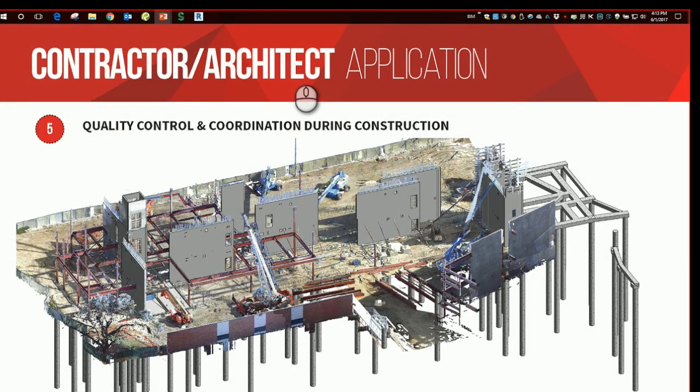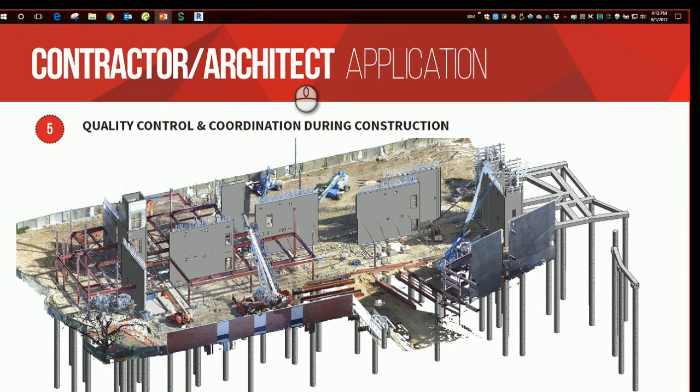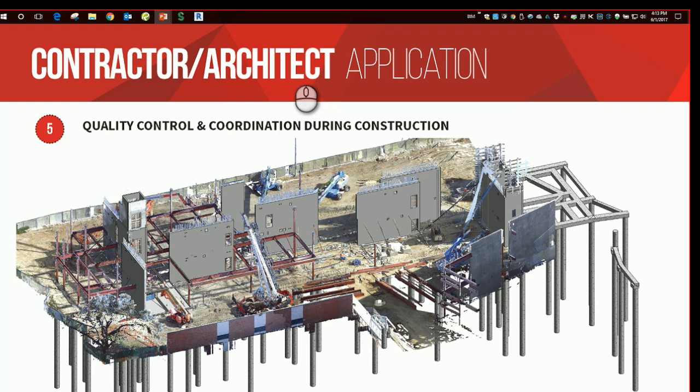This example shows the ability of the point cloud to enhance the quality and coordination of a project during construction. The image you see here is the point cloud overlaid to our structural concrete shear wall model. This enabled us to coordinate highly all the many openings that were required in these concrete shear walls.